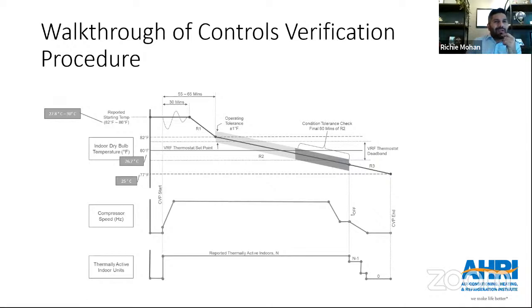There has to be a 3-minute interval such that the compressor speed, the fan speed, and the expansion valves are within a certain tolerance from what the manufacturer really wants to use. If they are within tolerance, then go ahead and use it. But if they're not, then you have to use whatever you found in this gray area as an average value for compressor speed, fan speed, and expansion valves, and carry it over to the steady state test.